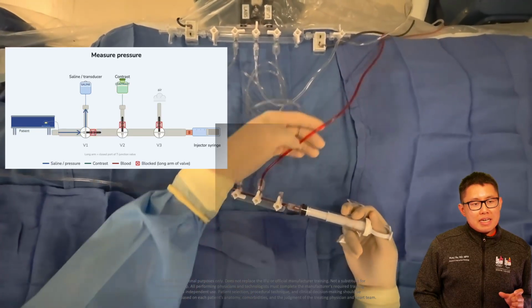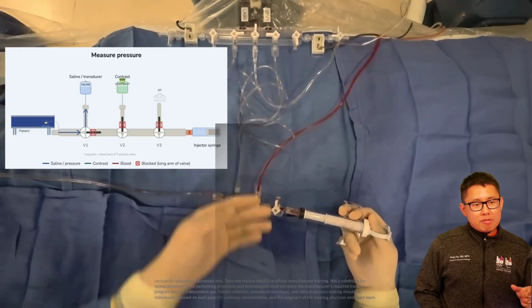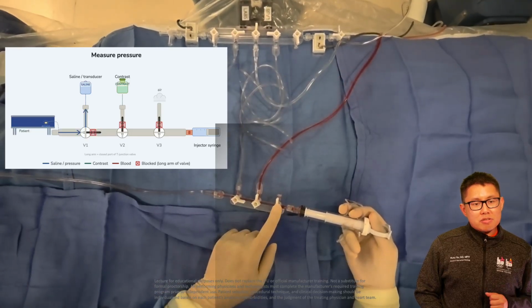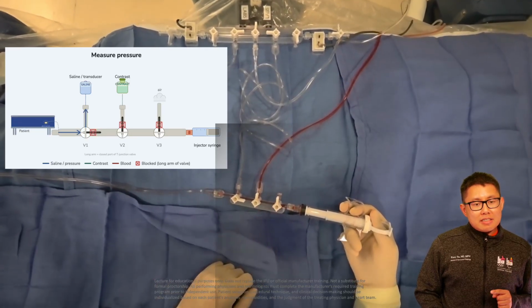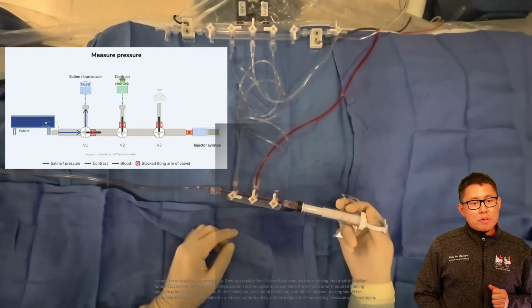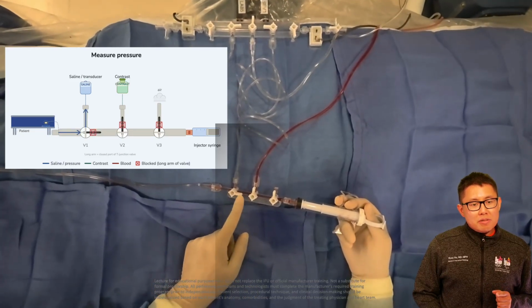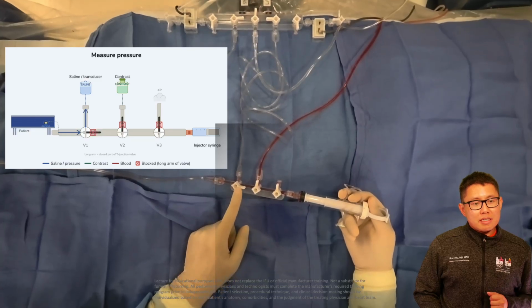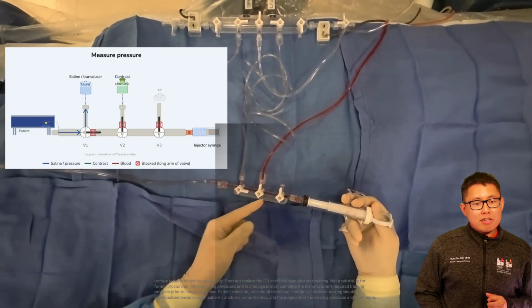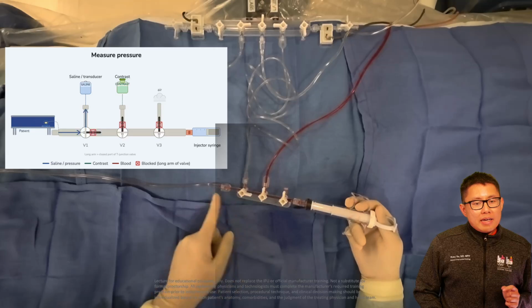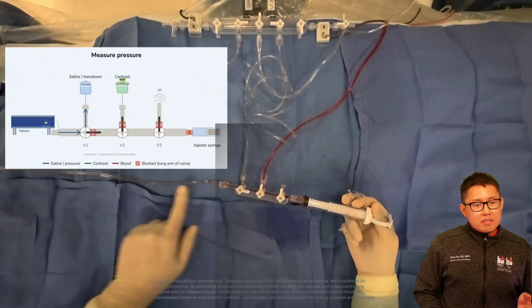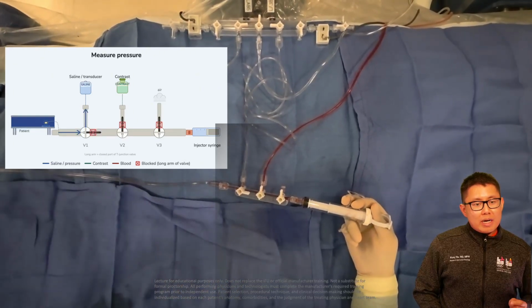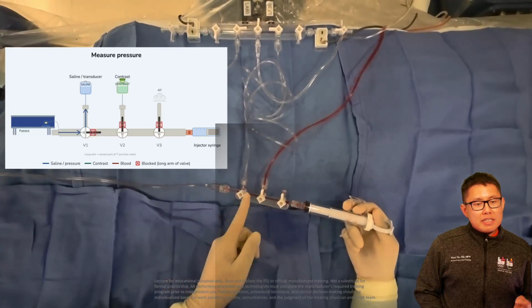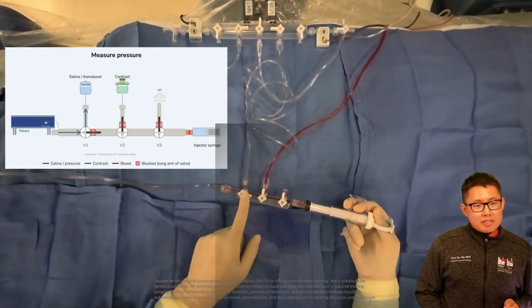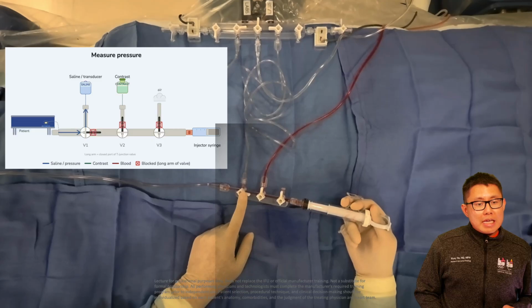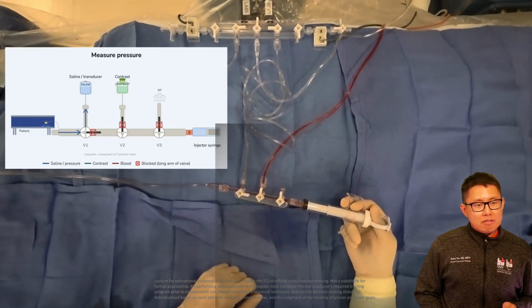For each of these, I show you a little inset of a diagram of what's happening, where the X shows the blocked side. V3 is connected to air in case we want to air out bubbles or we want to perform zeroing. And V2 is connected to the contrast bag or contrast reservoir. At all times, by default, you want to have V1 pointing towards the right so that your default position is pressure transduction, so that you can have continuous hemodynamic monitoring of the patient, which is what we see in this picture.